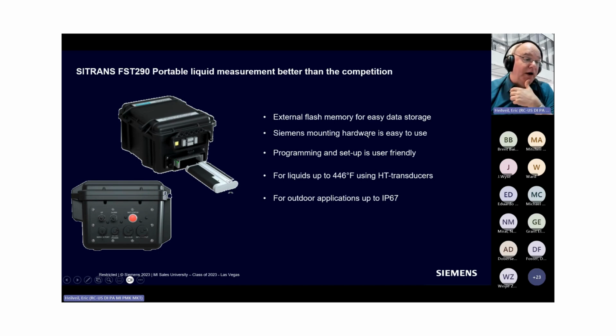The transducer hardware which comes with it is quite interesting. It can be permanently mounted, just like a regular set of transducers, but there are also magnetic mounts, with rare earth magnets, that you can just stick on there for a temporary mount to do a flow check or a flow verification or validation on another piece. Or if you have a valve that's closed, you put the transducer on, you can evaluate what the speed is and whether or not there's any difference upstream and downstream, and you can tell whether or not the valve is leaking. A lot of people use it for that.